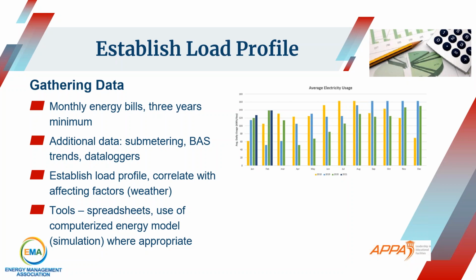You can gather additional data by doing sub-metering, if available through the BAS or your power monitoring system, or by installing data loggers. Then you want to establish that load profile, ideally by utility or by fuel source, correlating it with any affecting factors, typically on a monthly basis.